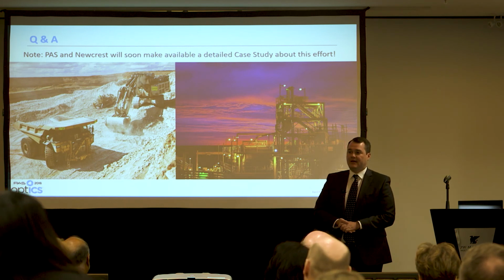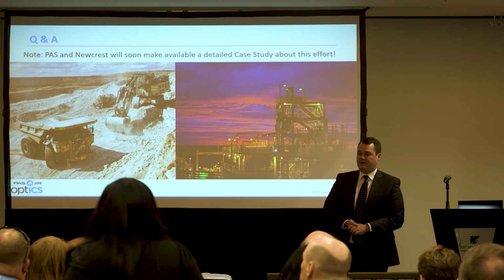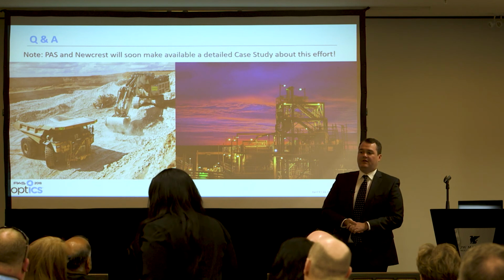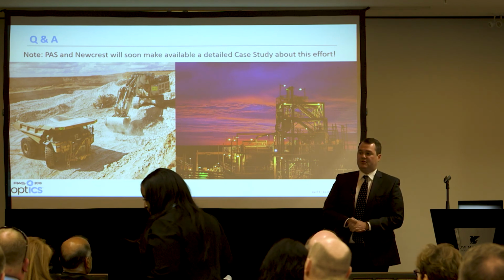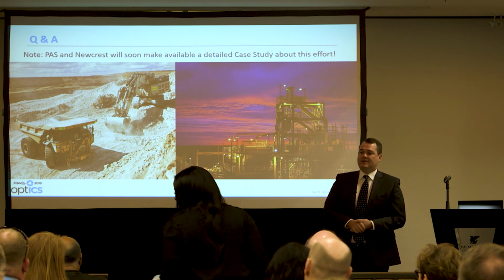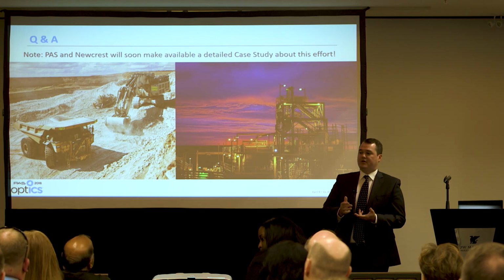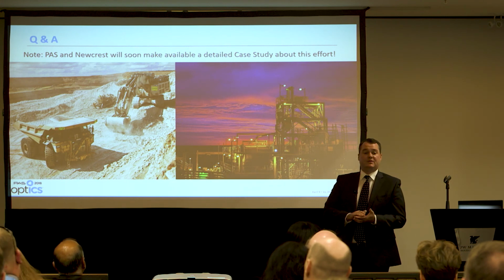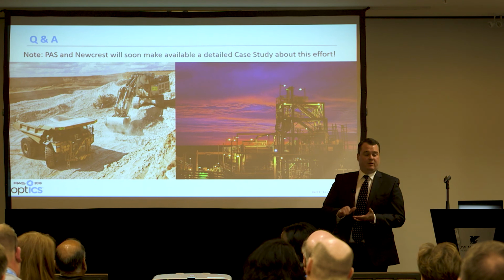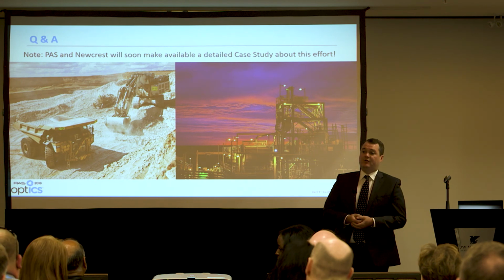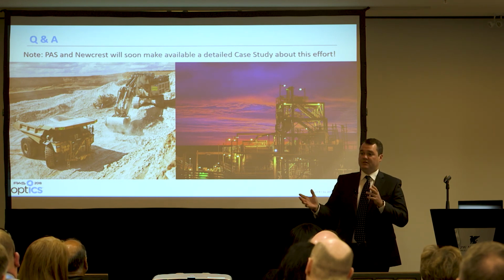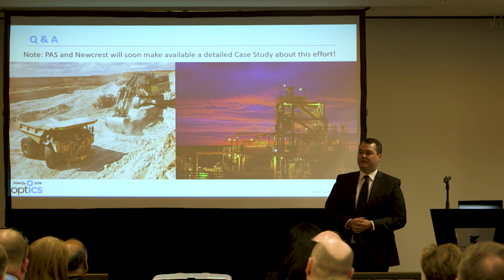Yes, we are still doing that. What we've done is create a maintenance priority list now - anything that's a condition-based alarm is being pulled out to a separate list. So that'll be your high vibrations, high temperatures, things like that, which are warnings more for the maintenance team. But we will still get some alarms through for critical bits of equipment - if the valve's not in position, it will still come through to the operator if it's critical.